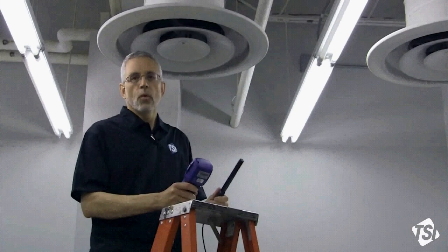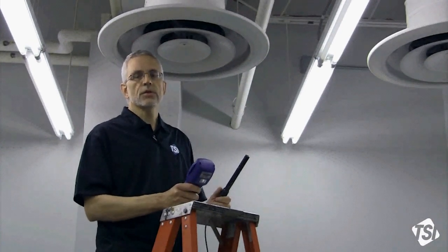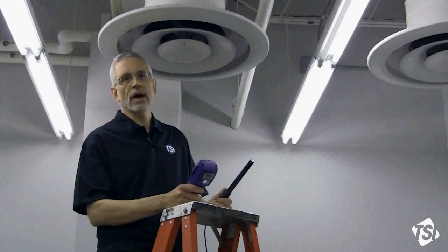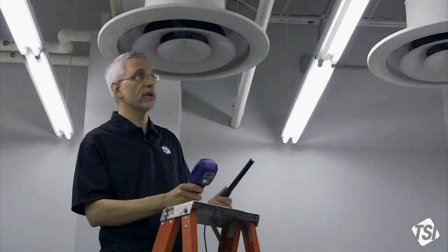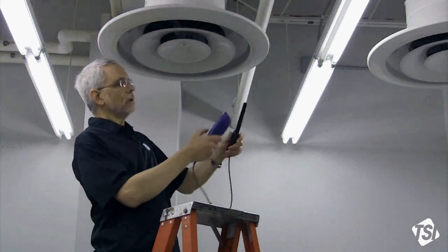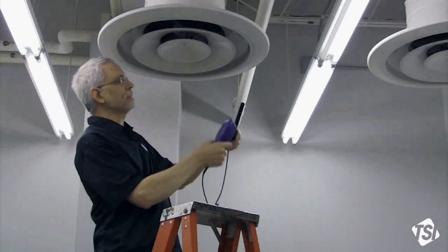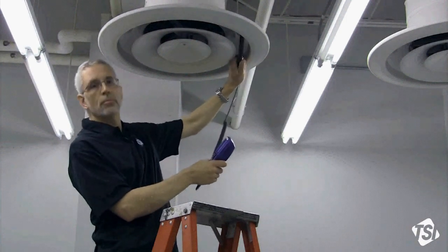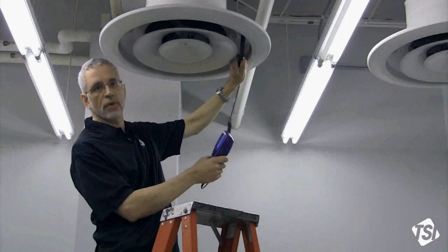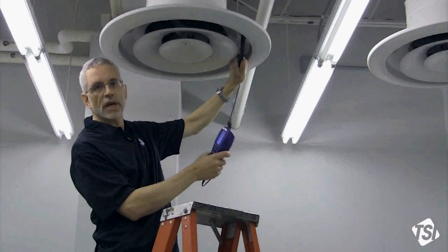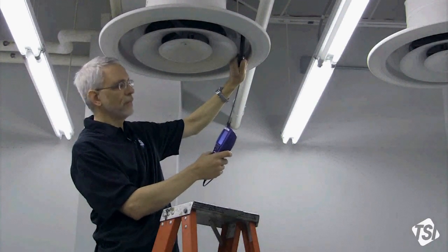Once inside, I select a suitable location to take my supply air concentration measurement reading. I press the down arrow to highlight the supply value, place the probe fully in the flow, allow a few seconds for it to stabilize. Then I will take the measurement by pressing the middle soft key.